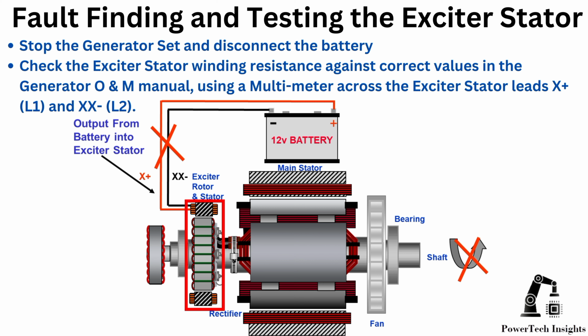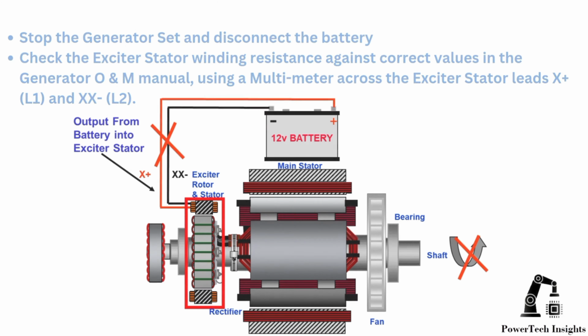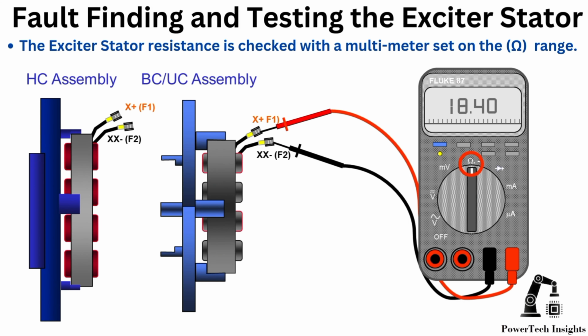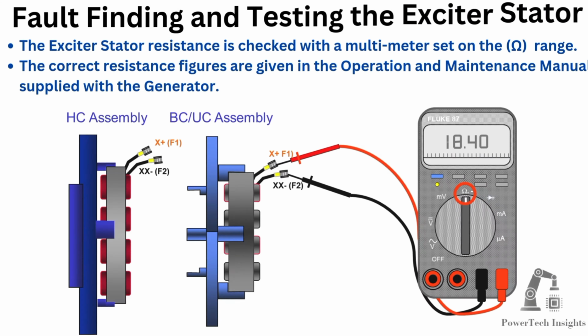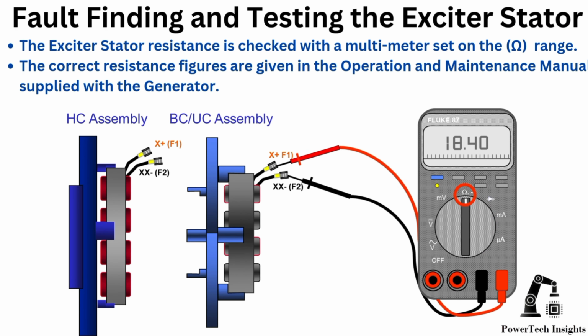Follow lockout-tagout, LOTO procedure. Check the exciter stator winding resistance against correct values in the generator O and M manual, using a multimeter across the exciter stator leads X plus and XX negative. The exciter stator resistance is checked with a multimeter set on the ohm range. The correct resistance figures are given in the operation and maintenance manual supplied with the generator.